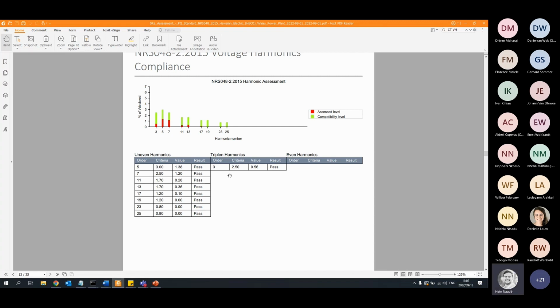The full list of triplen harmonics actually includes 3, 9, 15, 21. So they are special harmonics because in some situations you expect them to never be present, and it also goes as an indicator for your neutral earthing strategies.